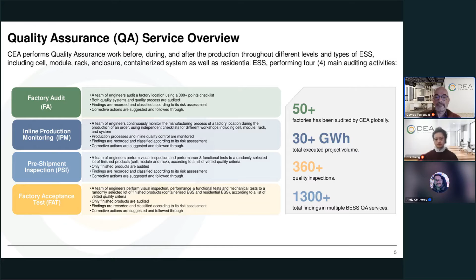Finally, when the system is integrated, we perform the factory acceptance test: visual inspection, performance, functional tests, and mechanical tests. This can be done on a 100% basis, but typically on a sampling basis of the DC blocks, containerized for utility scale, or if needed for residential batteries. Only the finished products are audited. Again, findings are recorded, classified, and corrective actions are suggested and must be followed and closed, otherwise the product cannot be shipped. This is the final step before shipment.